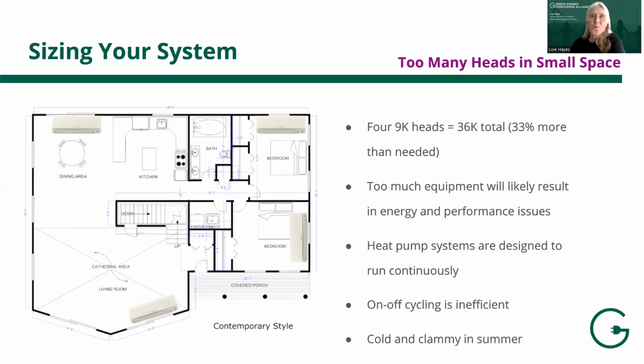Now, this is the one we want to warn you about. A contractor comes in and says, oh, your heat load is 24,000, but you need a head in every room. And so I'm going to put in 4 heads, and I'm going to put in the 9,000 BTU units. And it's fine that that's going to give you a max capacity of 36,000, because they'll just run less, and that'll be fine. But the problem is that you've now got a third more than what you need in terms of the BTUs being produced.